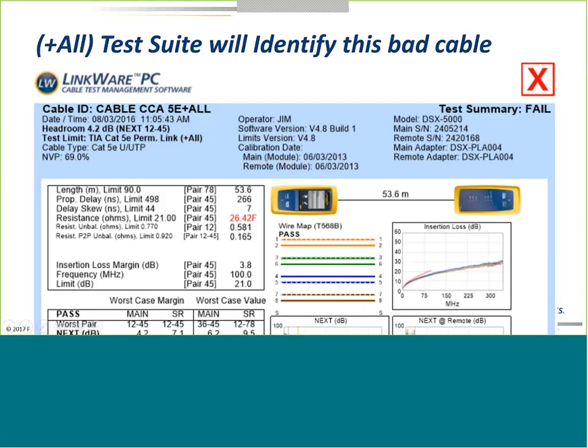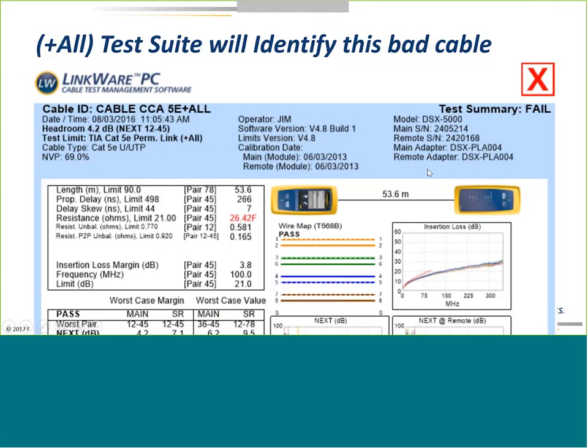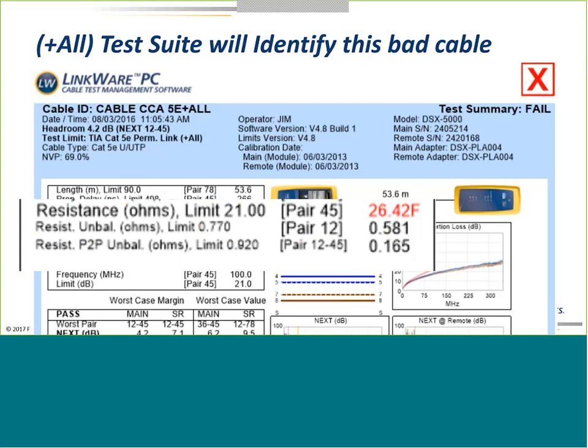The TCL test we'll save for another day. But running the resistance test with the limit applied on the same cable — 53.6 meters — including resistance and resistance unbalance: 26 ohms of resistance on only 50 meters of cable. Too much resistance — fail. Let's get this out of here.